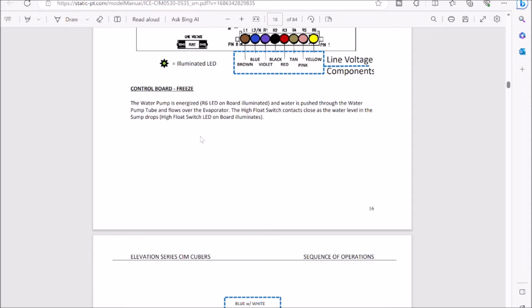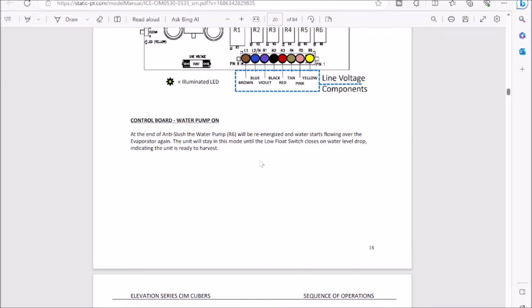And what we want to focus on here is what would cause an hour freeze. So now we're looking to see what would make a max freeze of 1 hour. So we need to know what terminates the freeze cycle. In our case, there's a low float switch. Once that closes on water level drop, it indicates the unit is ready to harvest. So we have 60 minutes for this to happen. So what could cause this not to happen?